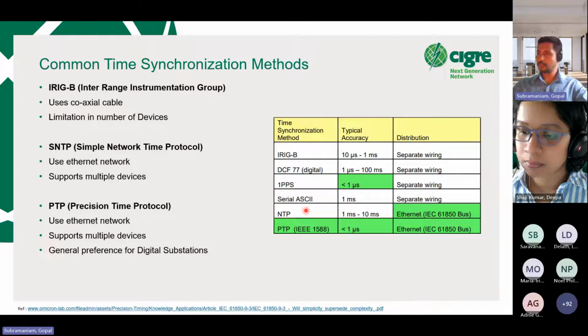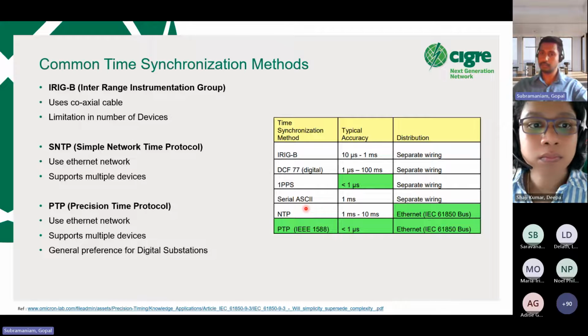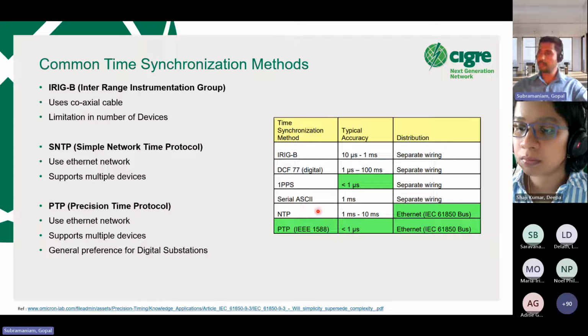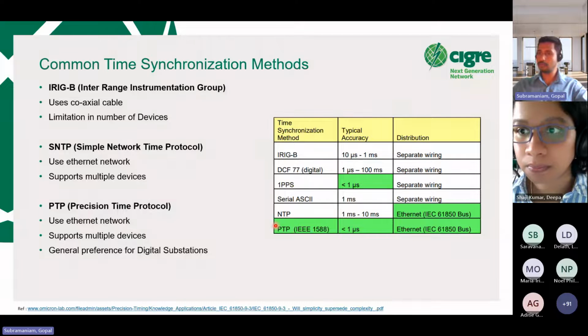And the most commonly used, where we have a station bus based 61850, is network time protocol, or SNTP. Compared to IRIG-B, SNTP has slightly lesser accuracy, but the limitation with IRIG-B lies in the cabling, the hardware. But network time protocol will be sufficient for a station bus protocol, and for GOOSE and MMS related signaling. But when we go into the completely digital substation, PTP is the preferred protocol.